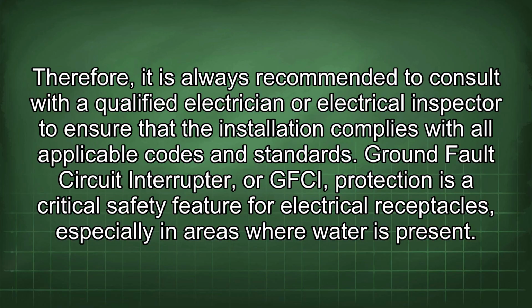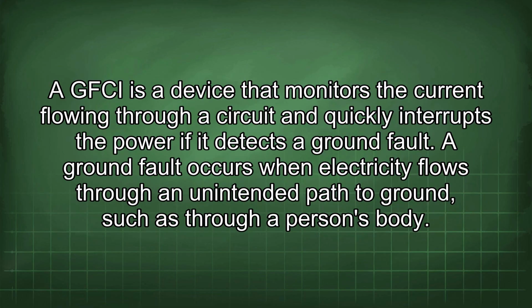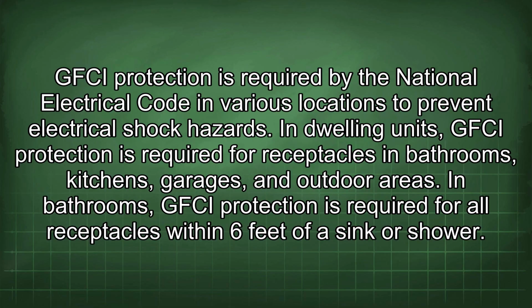Ground fault circuit interrupter, or GFCI, protection is a critical safety feature for electrical receptacles, especially in areas where water is present. A GFCI is a device that monitors the current flowing through a circuit and quickly interrupts the power if it detects a ground fault. A ground fault occurs when electricity flows through an unintended path to ground, such as through a person's body. GFCI protection is required by the National Electrical Code in various locations to prevent electrical shock hazards.